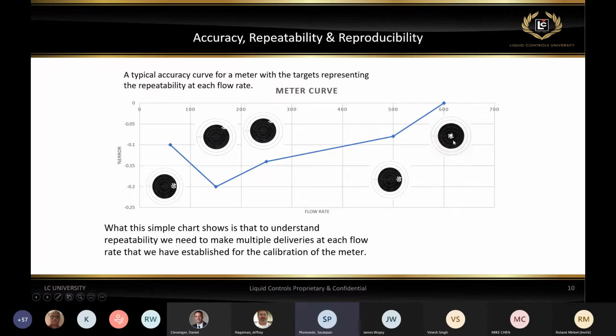Second, again, the meter was calibrated and zeroed out at 600 gallons a minute. So not only is it repeatable, but you also see all the points in a bullseye. So it's repeatable, but it's also an accurate meter at 600 gallons a minute. But what it also represents here is linearity, or accuracy across the range of the flow. If you look at high flow and low flow, the overall spread between those points is about 0.2%.